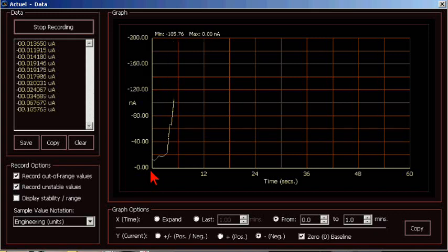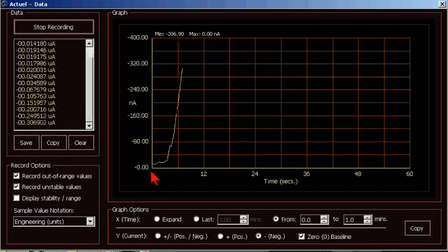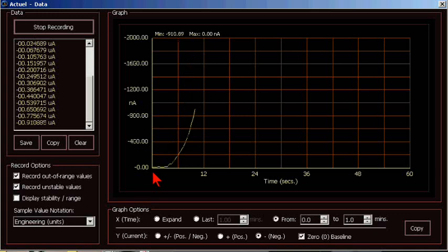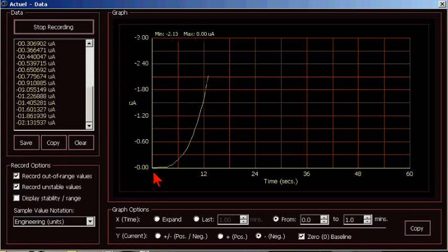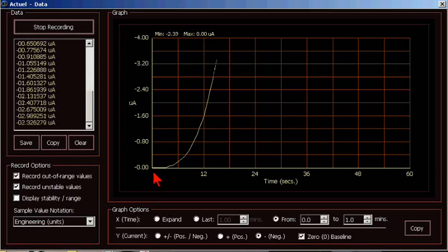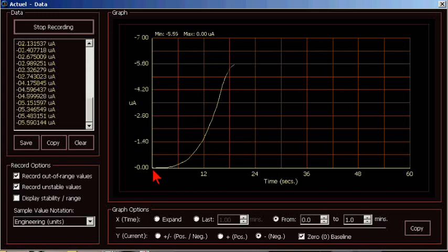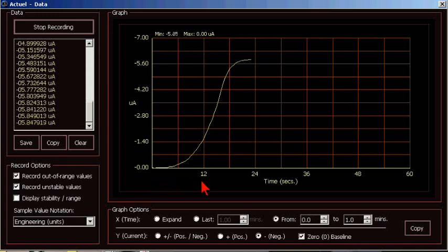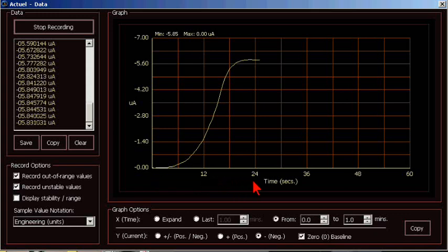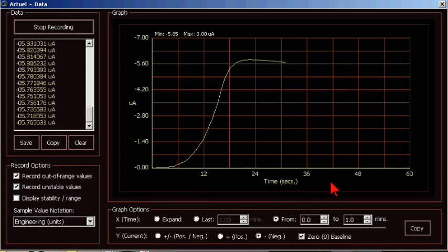Okay, let's record. You can see the data values are being recorded on the left and that the data is being graphed in this area. Note that the response time is slow due to having a high filter value. The X axis is showing the acquisition time in seconds. We'll acquire out past one minute so that we can look at some of the X options. Graphing current versus time can provide some really useful information that you just don't get with the standard picoammeter, such as beam current stability over time.